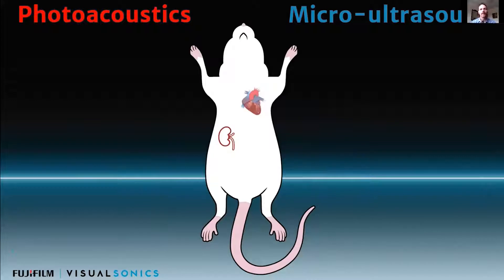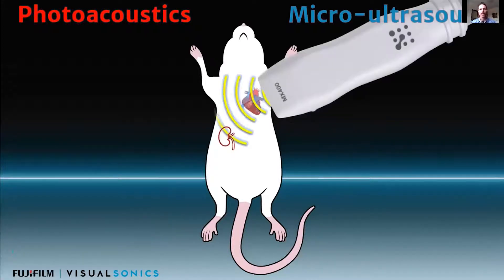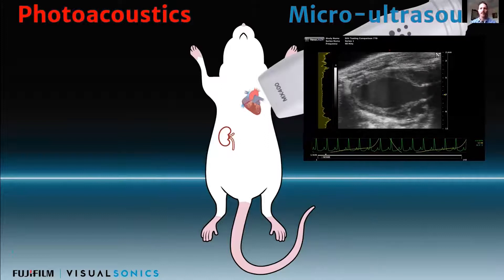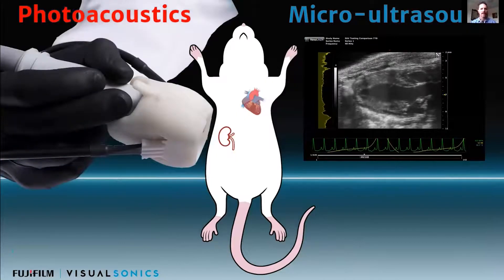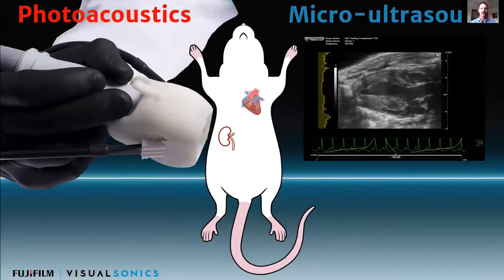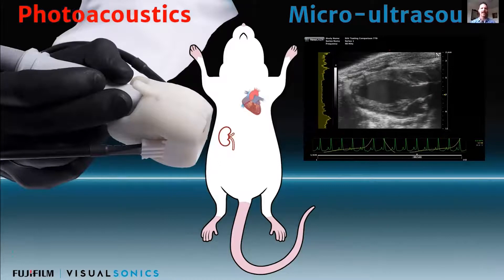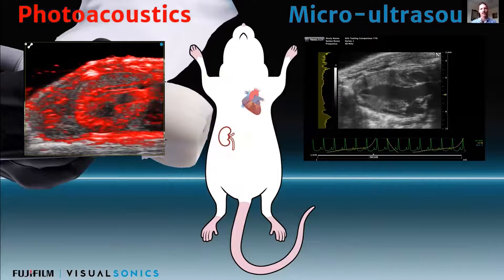So what is photoacoustics and micro-ultrasound? I use the term micro-ultrasound because we're using high frequency ultrasound. We send ultrasound waves into the tissue, those waves are reflected back, and we use that transducer to listen, forming a really nice high resolution image. With photoacoustic imaging, it's a hybrid imaging modality where we use light to stimulate the tissue to generate an ultrasound signal — pulse laser light shines into the tissue, generating a thermoelastic physical effect, which results in a pressure or ultrasound wave.